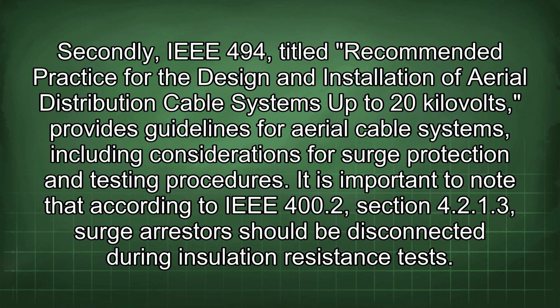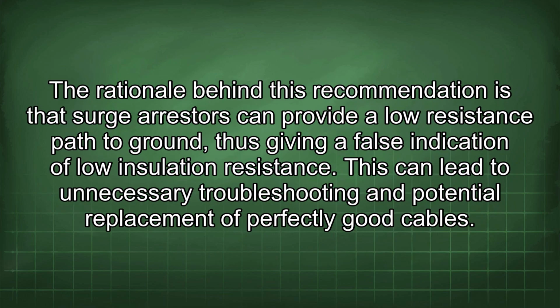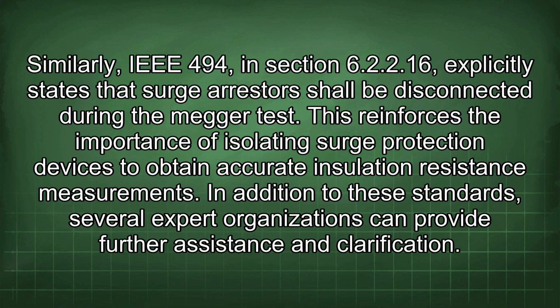It is important to note that according to IEEE 400.2, Section 4.2.1.3, surge arrestors should be disconnected during insulation resistance tests. The rationale behind this recommendation is that surge arrestors can provide a low resistance path to ground, thus giving a false indication of low insulation resistance. This can lead to unnecessary troubleshooting and potential replacement of perfectly good cables. Similarly, IEEE 494 in Section 6.2.2.16 explicitly states that surge arrestors shall be disconnected during the Megger test. This reinforces the importance of isolating surge protection devices to obtain accurate insulation resistance measurements.